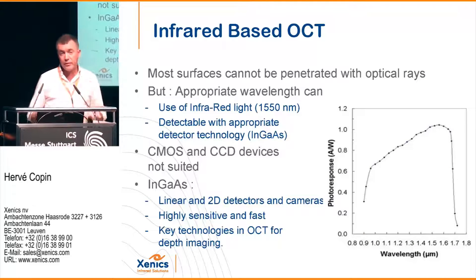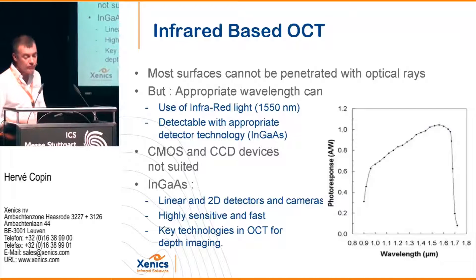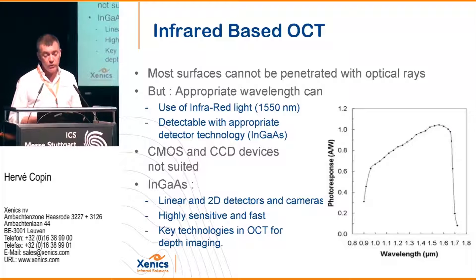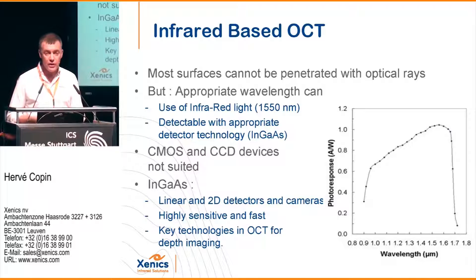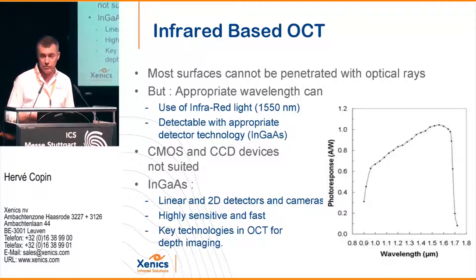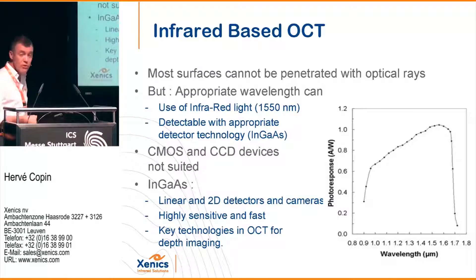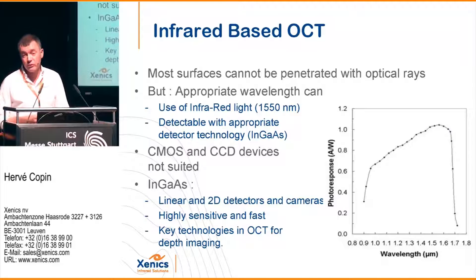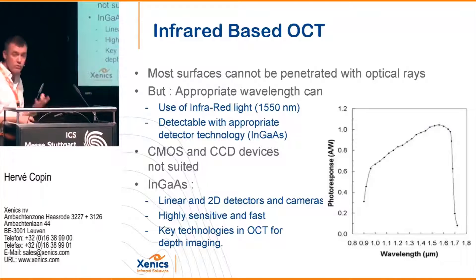Why use infrared instead of visible light for OCT? Shortwave infrared can penetrate several materials much more than visible light. Using shortwave infrared from 0.9 to 2.5 micrometers, you can go deeply into the material — up to 6 mm depth, which is much more than visible light allows. For that you need to use a special sensor developed at Xenics: InGaAs sensors, because CMOS or CCD are not sensitive beyond 1 micron. This sensor type is needed to detect light at those various wavelengths.